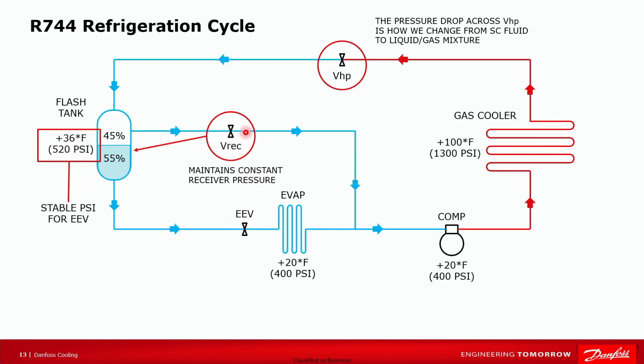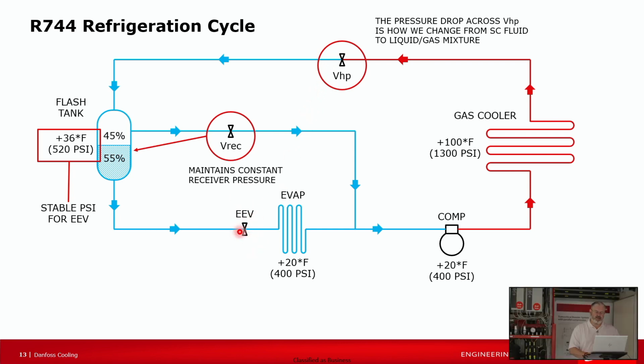If you think about the receiver valve not being in place, and the expansion valves at your cases seeing the changes at the high pressure valve, they would hunt continuously. It's a superheat controller, so with that variation all the time from the high pressure valve, you would have the EEVs chasing their superheat the entire time. So the receiver valve deals with the flash gas to keep it from going to the evaporator, but it also helps provide a steady pressure at the expansion valve.